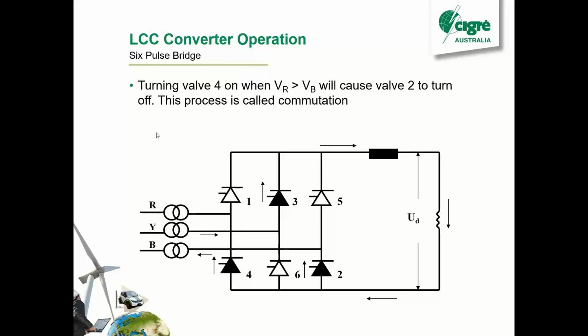We'll turn on valve 4 with our gate pulse. And then if everything's all good, valve 2 will turn off by itself because of the AC system turning it off. So you can see right now why you need an AC system, why you can't do a black start with the LCC. Because if you don't have this AC system to turn off that other valve, you'll get what we call a commutation failure, and the converter will cease to work.